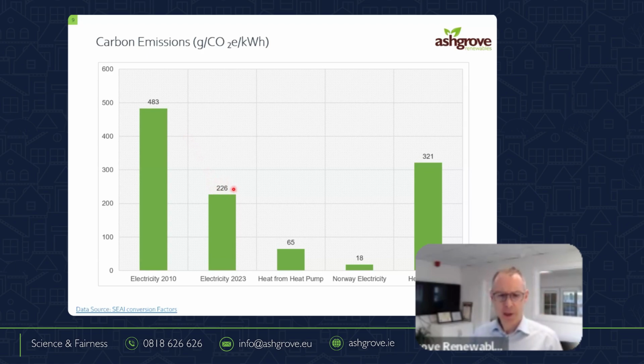But when I put a heat pump with that at a 350% efficiency or a COP of 3.5, I simply take that 226, I divide it by 3.5, and I get 65. What's interesting is compared to oil, obviously, you can see it over here, 321 if the oil boiler is 90% efficient. But what's interesting here is we have a long way to go in Ireland on our decarbonisation of electricity journey, and we don't need to look too far.